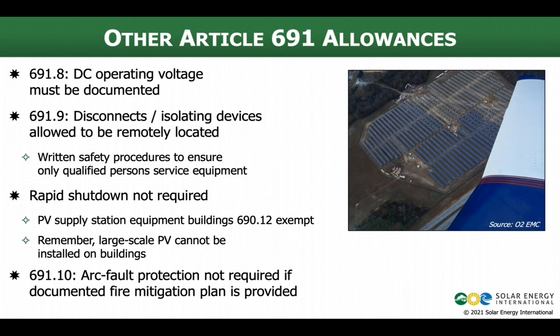And 691.10 says arc fault protection is not required so long as there's a documented fire mitigation plan. So arc fault protection, fundamentally about fires, preventing them from happening. In this case, we are allowed to have a fire mitigation plan. It's probably going to have to be approved by the local fire official, involving things like clear spaces and access and materials that are on hand in order to prevent a wildfire from spreading outside of the fence. Because that's really the issue here.